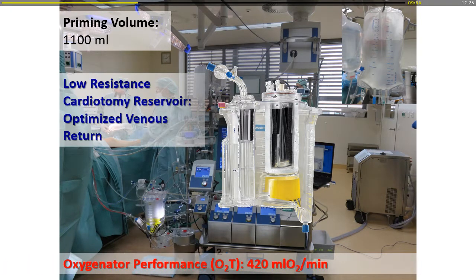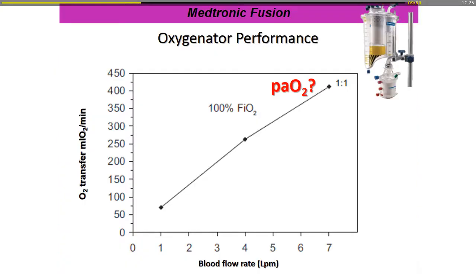Now, oxygenator performance. I did a study on this, and it actually goes up to 420 milliliters of oxygen per minute. When you look at oxygenator performance, we're given this information that's in the book: it goes up to 7 liters a minute and has an oxygen exchange of 420. But we're not given what the PO2s are. One oxygenator can say I go up to 8 liters, but the PO2 is much lower than the other one that goes up to 7 liters.